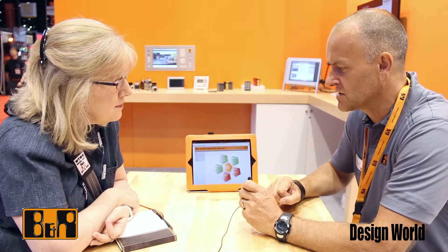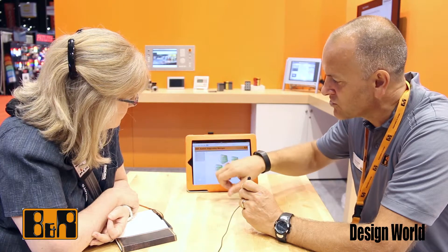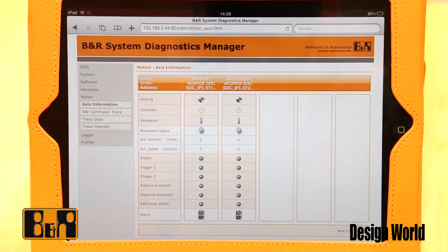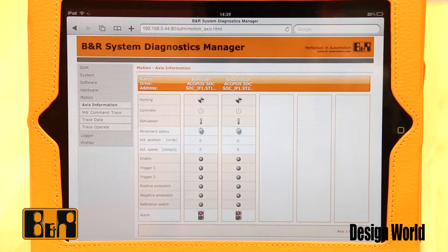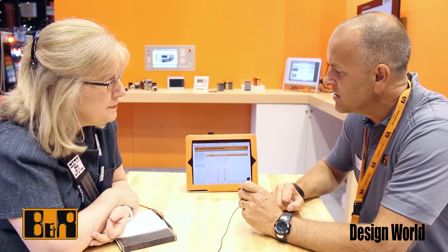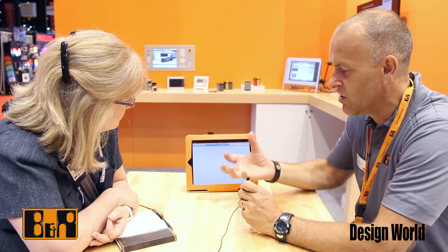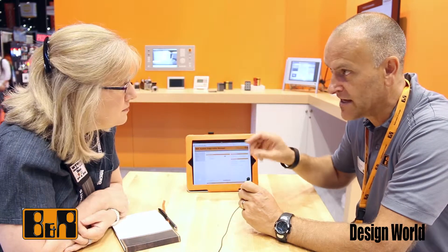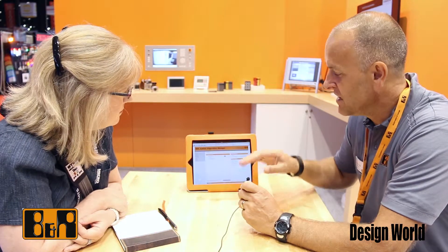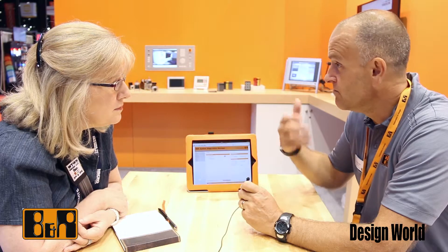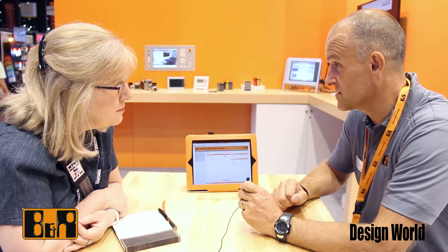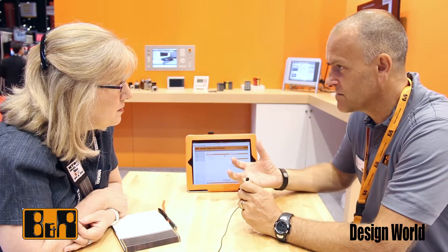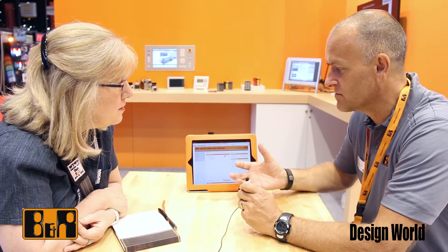You can get full diagnostic information including things like motion control. You can see the axes on the system, which will show you what's happening on each axis. You can get traces from the axes, get error information from the axes. You can see the IO on the system — it will show you all the parts of the IO that are working, and if there's any IO missing, it will show a little red X or an exclamation mark depending on the error. It will tell you: module not functioning, module missing, or incorrect module placed into the IO configuration.